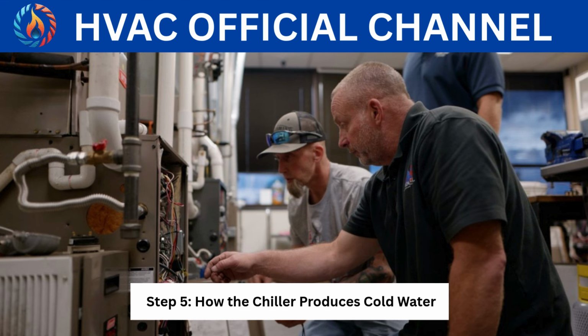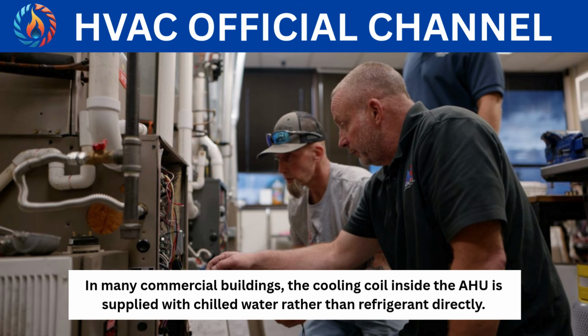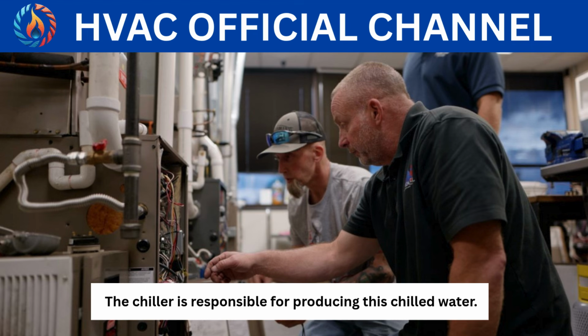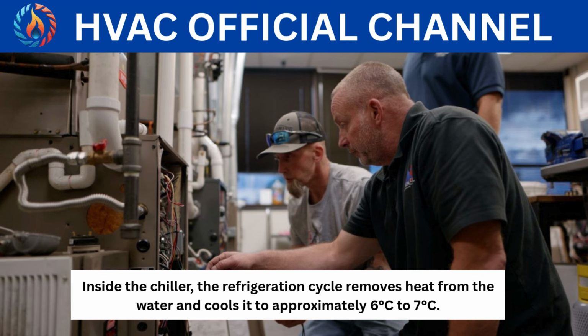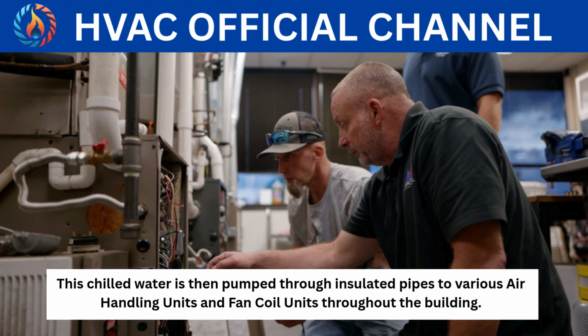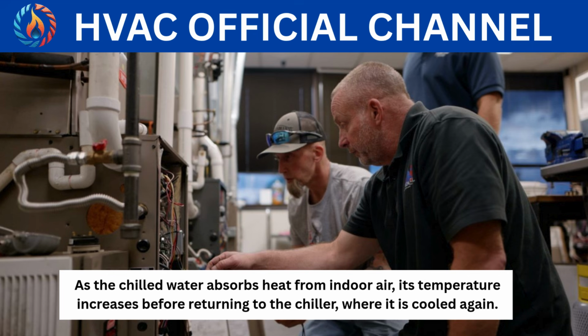Step 5. How the chiller produces cold water. In many commercial buildings, the cooling coil inside the AHU is supplied with chilled water rather than refrigerant directly. The chiller is responsible for producing this chilled water. Inside the chiller, the refrigeration cycle removes heat from the water and cools it to approximately 6 degrees Celsius to 7 degrees Celsius. This chilled water is then pumped through insulated pipes to various air handling units and fan coil units throughout the building. As the chilled water absorbs heat from indoor air, its temperature increases before returning to the chiller, where it is cooled again.